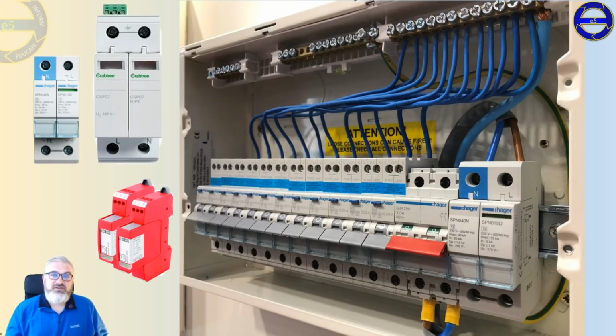So that's another risk. That's potentially another label, which isn't in BS 7671, we may want to put on the boards. So for you contractors out there, if you're installing 18th edition compliant boards, make sure you have a label that clearly states surge protection fitted and what the consumer has to look for when the surge protection comes to the end of its life or is damaged protecting the fixed installation.